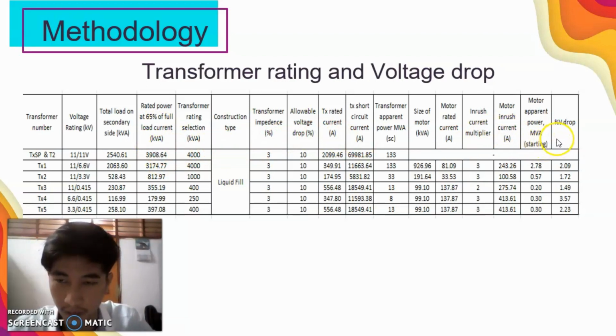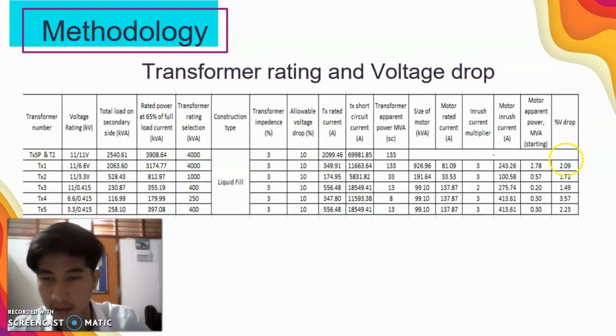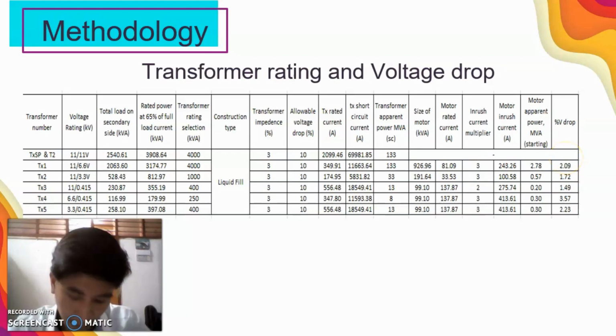Also for the voltage drops, we can identify which transformers fulfill criterion 2, which is that the largest motor starting at the secondary must be less than 10%. So for all the transformers, you can see 2.09, 1.72, 1.49, 3.57 and 2.23 are all less than 10%.